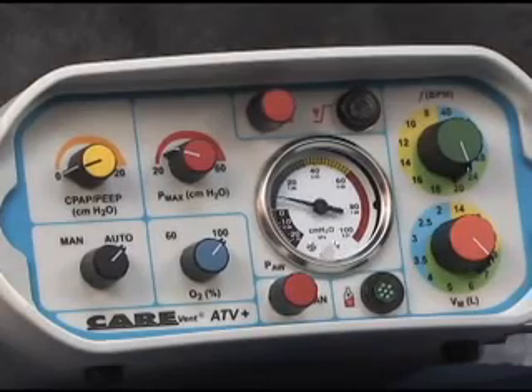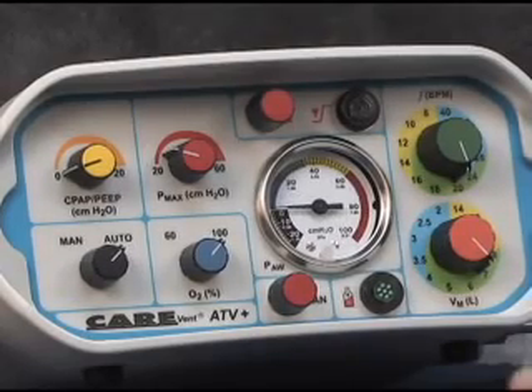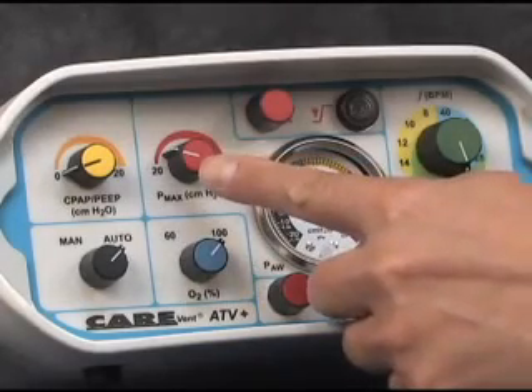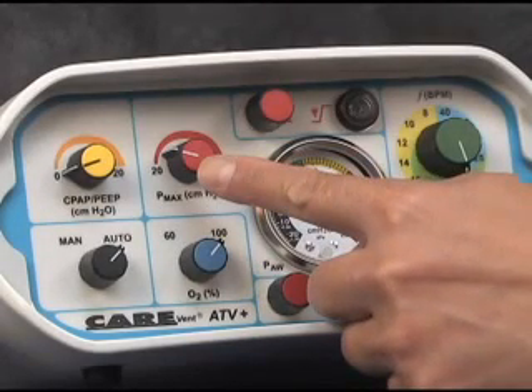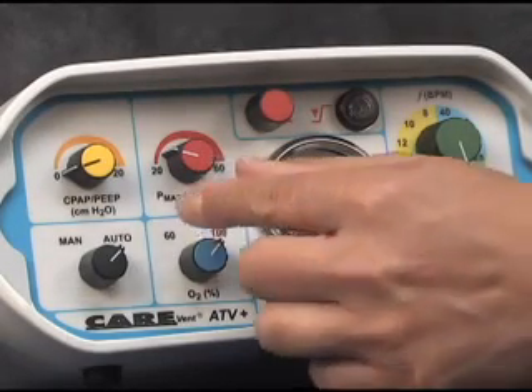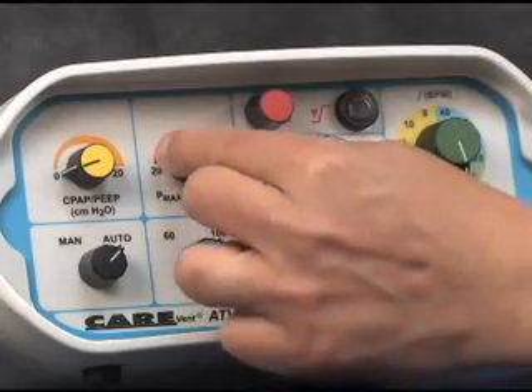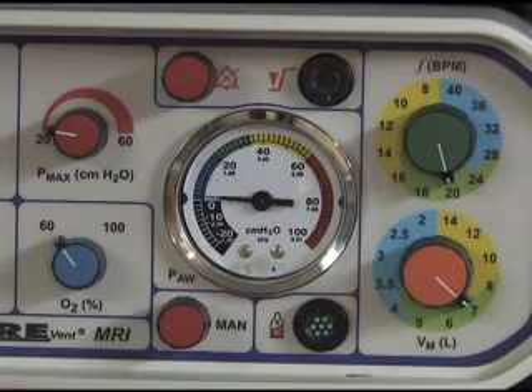Overinflation is prevented or airway blockage indicated by the operation of the adjustable pressure relief system. This provides a range of peak airway pressures from 20 to 60 centimeters of water. Exceeding the selected pressure will cause the airway overpressure alarm to activate, and a continuous tone will be heard during the inspiratory phase of the ventilator cycle.